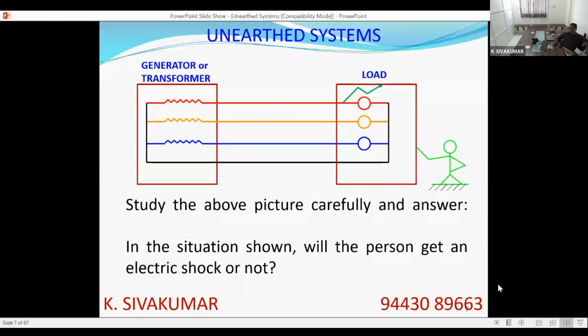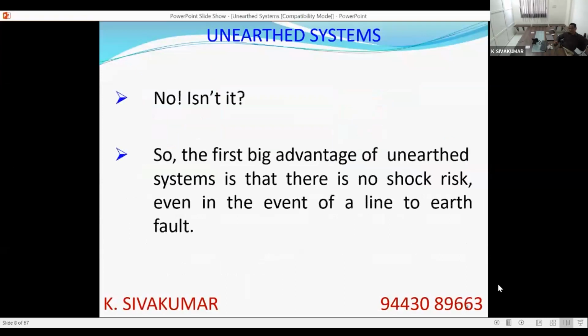To make a start, we will understand that since there is no closed circuit, there will not be any current flow. Shock is a matter of current flow through the human body. So let us make an understanding at present that since there is no closed circuit in this system, even though voltage is prevailing, there will not be current flow through the human body, and there will not be any shock. So the first big advantage of an unearthed system is there is no shock risk, even in the event of a line to earth fault, assuming that the capacitances are negligible. If the capacitances are significant, yes, the capacitive discharge may affect the person. But to simplify things, we will assume that negligible capacitance is there.